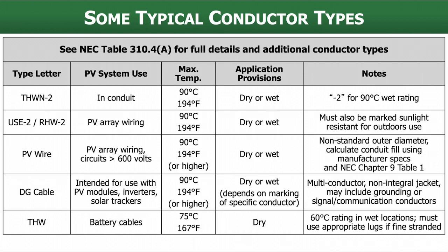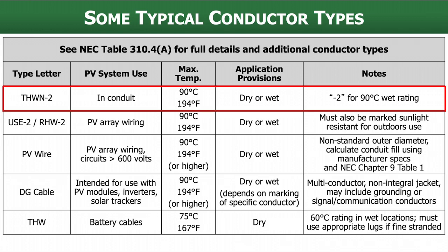One conductor we use a lot in conduit is THWN-2. It has a maximum temperature rating — that would be its insulation rating — of 90 degrees Celsius. That dash-2 tells us it has that 90°C rating in wet conditions, so it can be used in both dry and wet conditions. A conduit outdoors is considered a wet condition. This is what we typically run in conduit for DC wiring and AC wiring — a very common type of conductor.